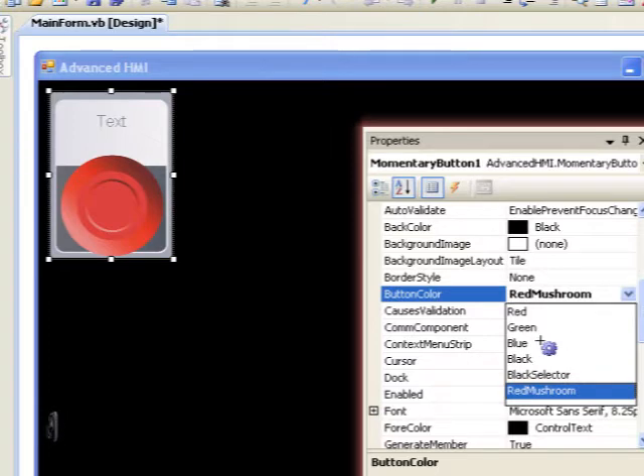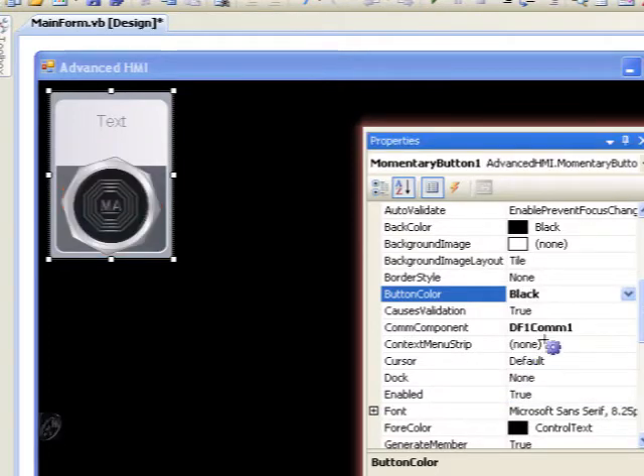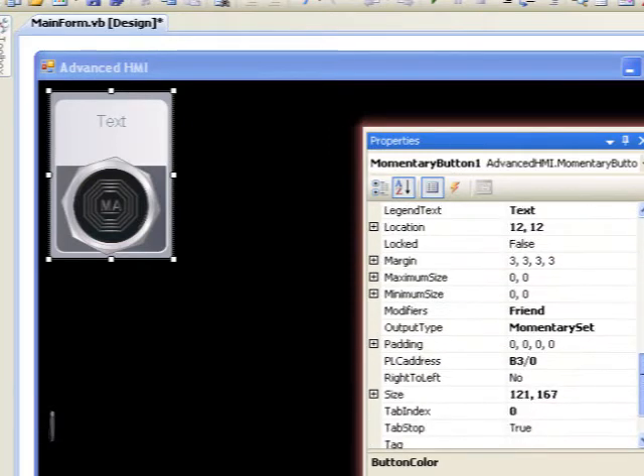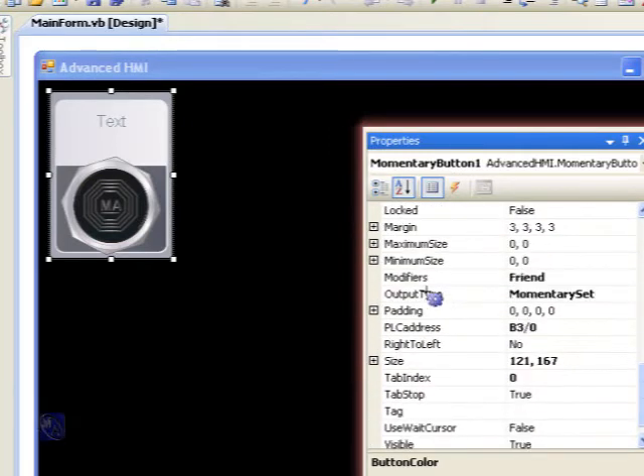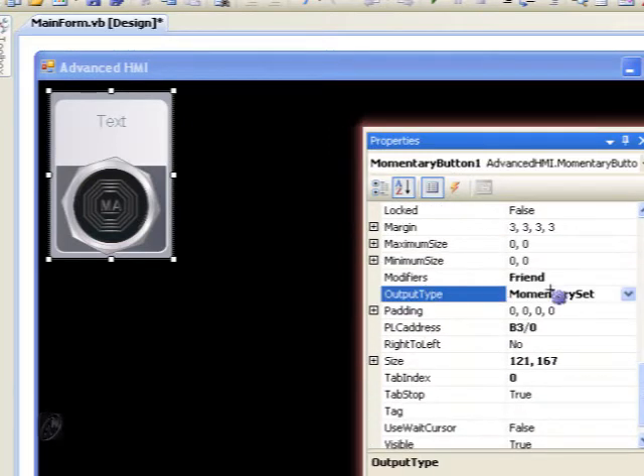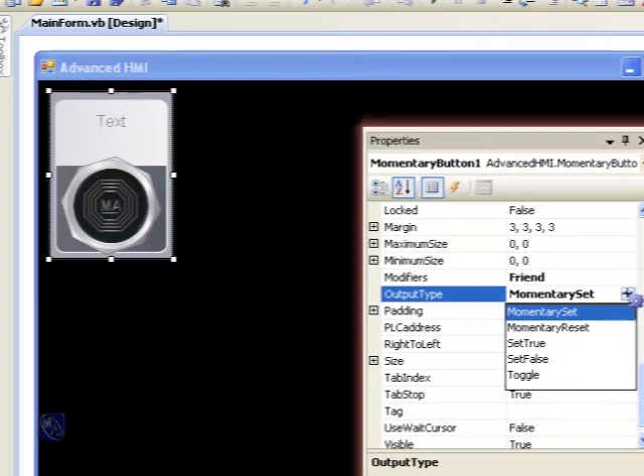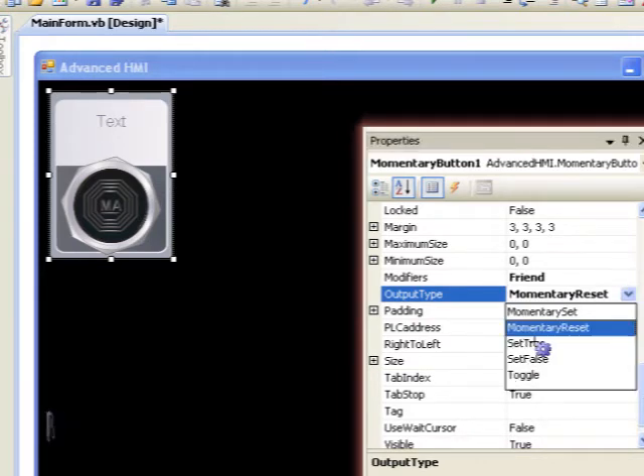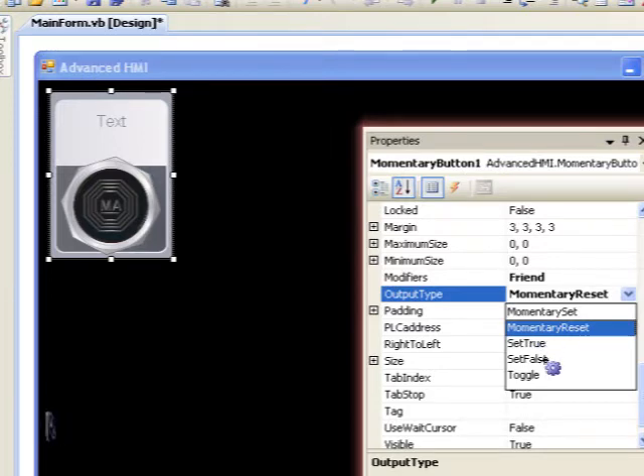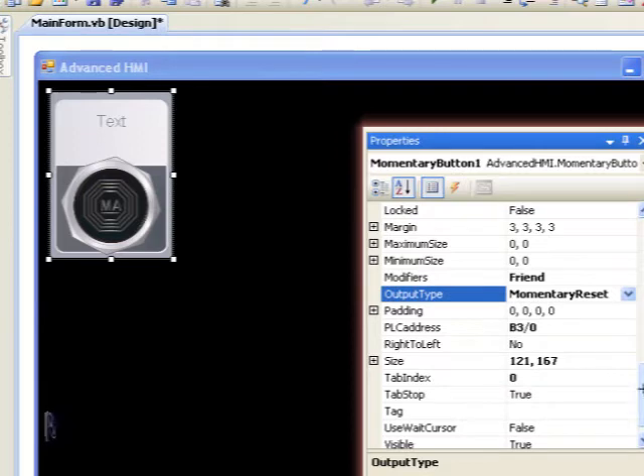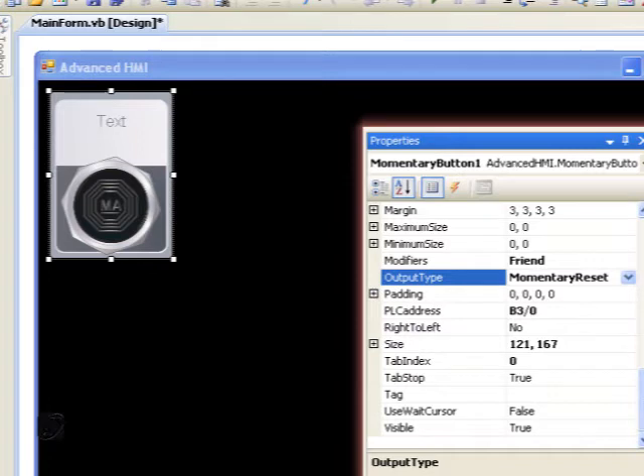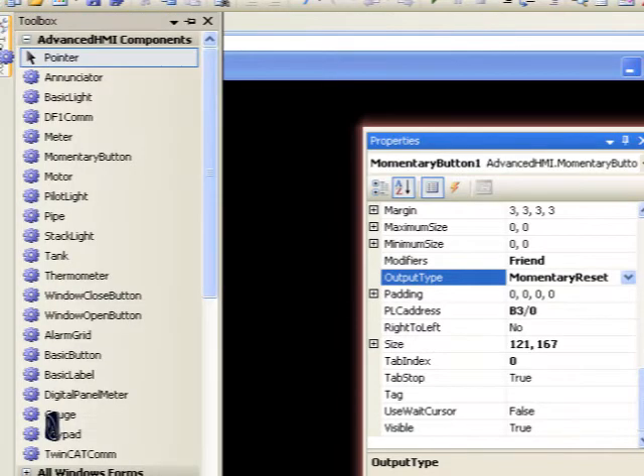So let me change that back to black, and I'm going to scroll down and show the output type. Now this is how it acts on the bit within the PLC. Here are options: momentary set, momentary reset, set true, set false, and toggle. The momentary set by default means when the button's being held, the bit will be true. When it's released, the bit goes false, and momentary reset is of course the reverse of that.